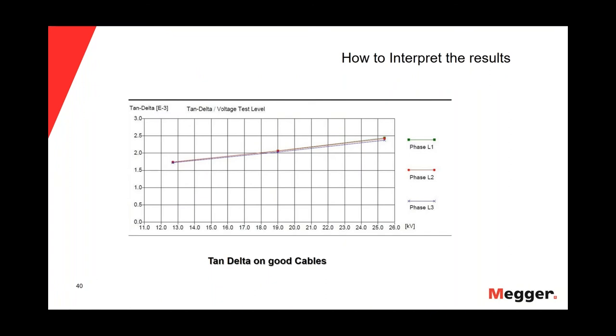As many tan delta measurements we have for a cable, the easier it will be to make a decision. We recommend that after the fifth year of the cable, we start with the tan delta test. That way we will have many measurements when we need to make an assessment regarding replacement. In this slide, we are seeing what we consider a good cable — there is some voltage dependency of the tan delta, but it's not significant. All three phases of this circuit appear okay and we could return this circuit to service, repeating the test in three or four years.